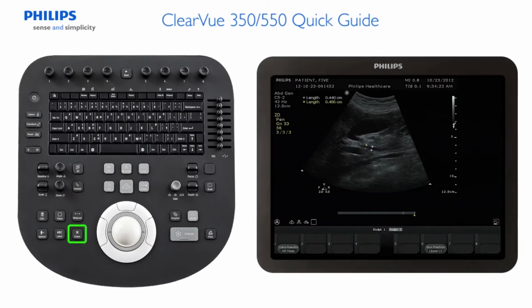The Erase button can be used to erase on-screen measurements. To reactivate a set of calipers on the frozen image, press the Measure key to launch another caliper. Using the trackball, position the amber caliper over the existing white caliper on the image until the white caliper changes to amber. Press the middle trackball button to refresh the white caliper, and use the trackball to reposition the caliper. Use the left or right trackball button to toggle between calipers. Press the middle trackball button to set the measurement. Please note that the function of the left and right trackball buttons can be customized in the Setup menu.